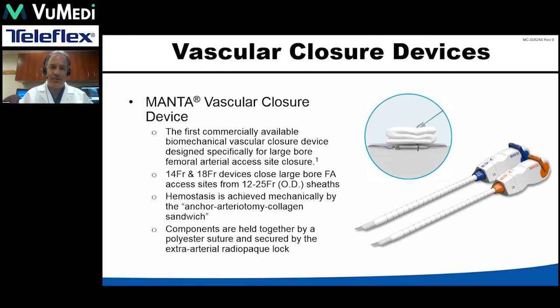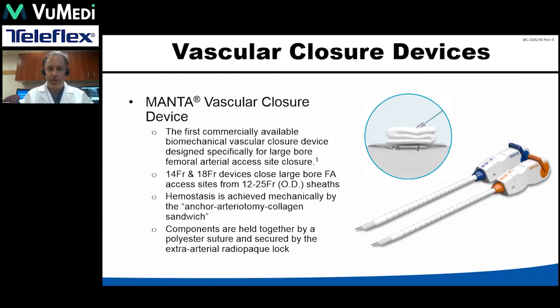Next, we'll talk about the Manta vascular closure device. This is the first commercially available biomechanical vascular closure device designed specifically for large-bore femoral arterial access site closure. Manta has 14 French and 18 French devices, used to close large-bore femoral arterial access sites from 12 to 25 French outer diameter sheaths — covering all of the standard sheaths we use today for our TAVR procedures. Hemostasis is achieved mechanically by the anchor-arteriotomy-collagen sandwich, and the components are held together by a polyester suture secured by an extra-arterial radiopaque lock.